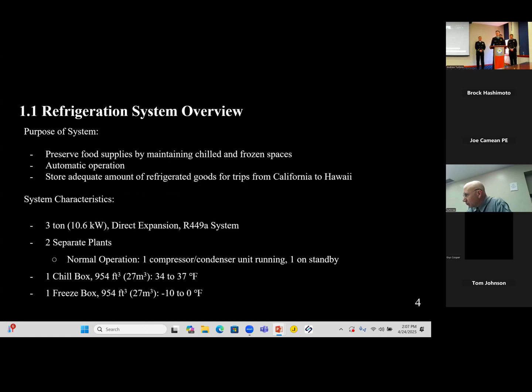The purpose of the system is to provide food supplies that are maintained and preserved, chilled and frozen spaces that are preserved to prevent spoilage when traveling from California to Hawaii. Additionally, the plant is requested to automatically operate based on different pressure switches on the compressor as well as the condenser. Lastly, there is required to be the adequate amount of refrigerated goods to and from California to Hawaii based on the volumetric capacity of each chilled and refrigerated space.